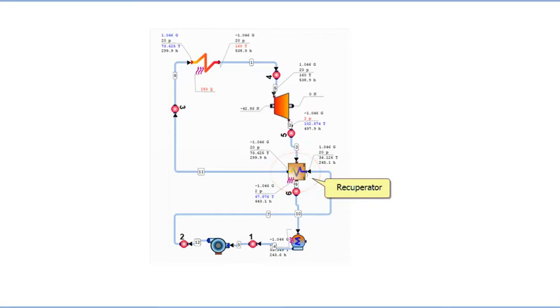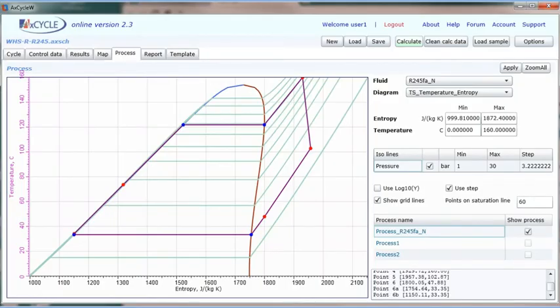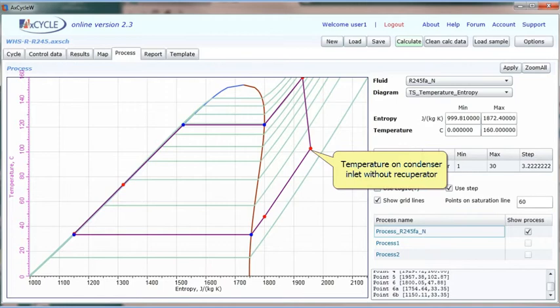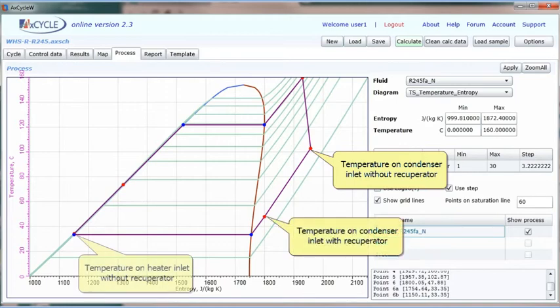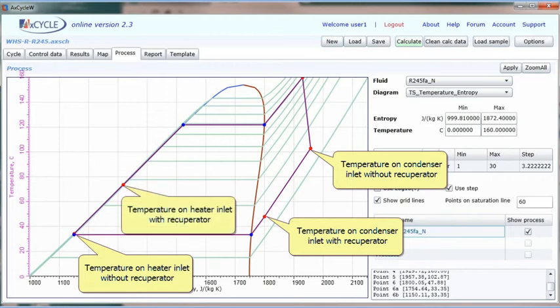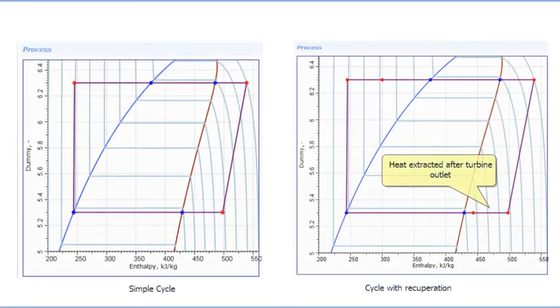Recuperation is used to increase cycle efficiency. In a recuperated cycle, a heat exchanger is placed downstream of the turbine, allowing preheating of the fluid before it reaches the heater. The temperature-entropy diagram shows the amount of heat extracted before the condenser with the recuperator, which is used to preheat the fluid at the heater inlet. The temperature at the condenser inlet is significantly lower and the temperature at the heater inlet is increased, helping to increase cycle efficiency. The pressure-enthalpy diagram also illustrates the heat extracted and used for preheating.